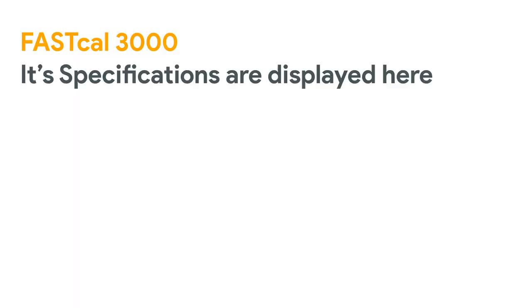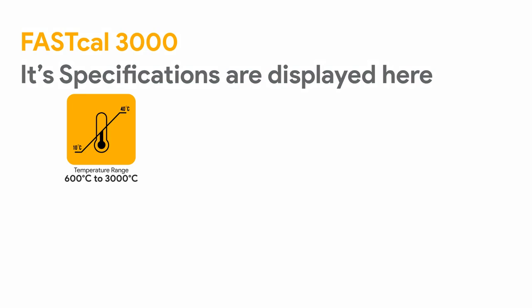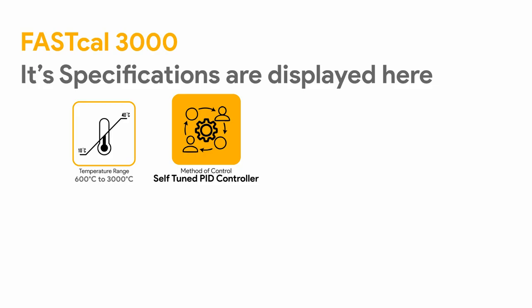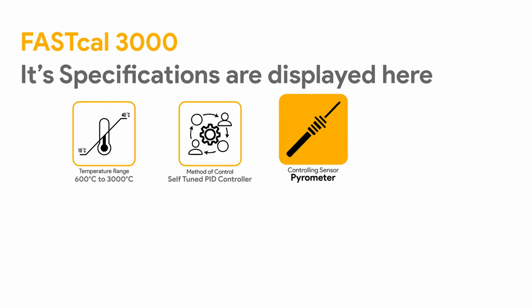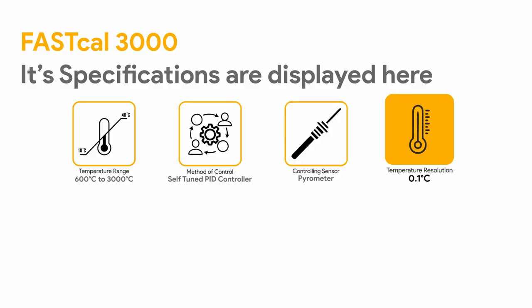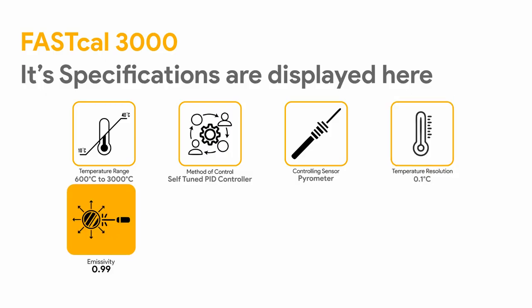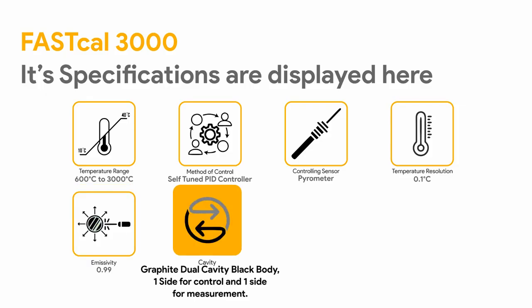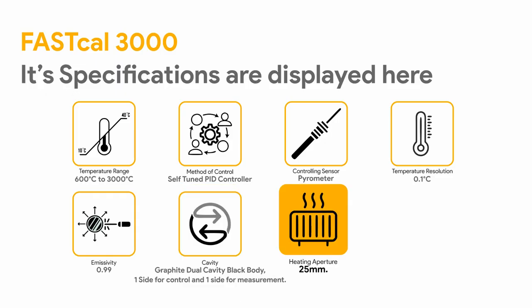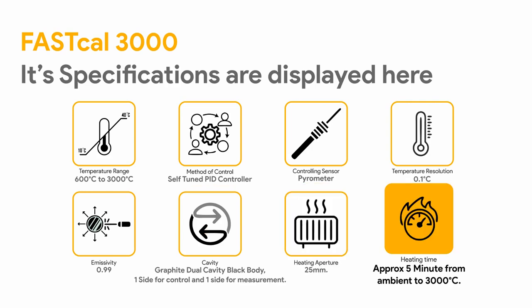Its specifications are displayed here. Temperature range: 600 degrees Celsius to 3000 degrees Celsius. Method of control: self-tuned PID controller. Controlling sensor: pyrometer. Temperature resolution: 0.1 degrees Celsius. Emissivity: 0.99. Cavity: graphite dual cavity black body, one side for control and one side for measurement. Heating aperture: 25 mm. Heating time: approximate 5 minutes from ambient to 3000 degrees Celsius.